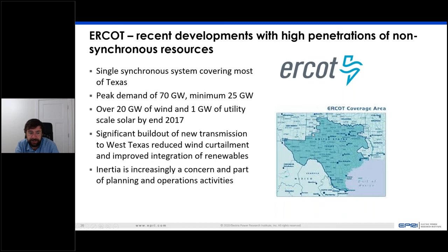They've also been looking more at inertia themselves, examining this over many years, and have shown that as wind penetration increases, system inertia does go down. However, they've found it doesn't go down far enough yet to be a real challenge, so they have monitors in their control room to flag system operators if there is an inertia-related issue.